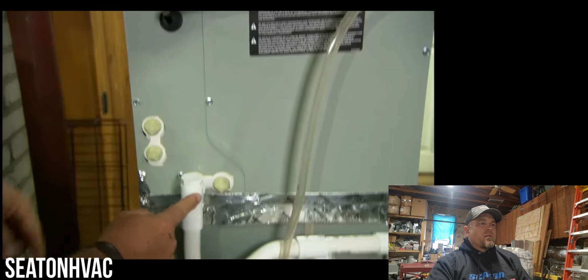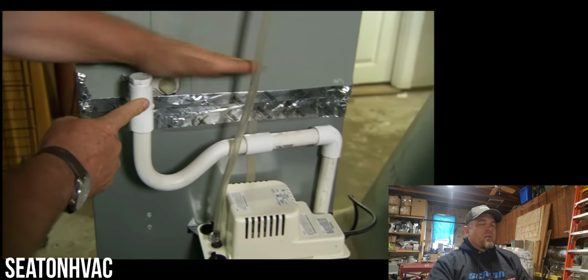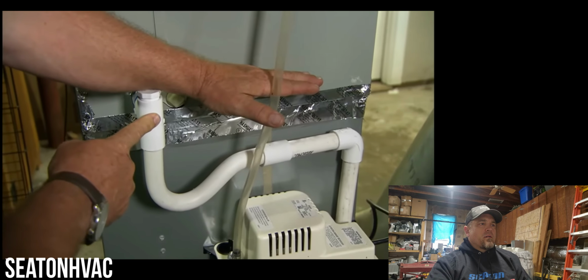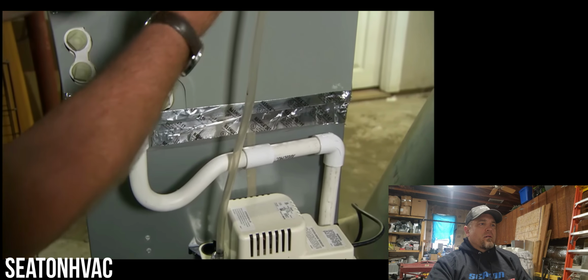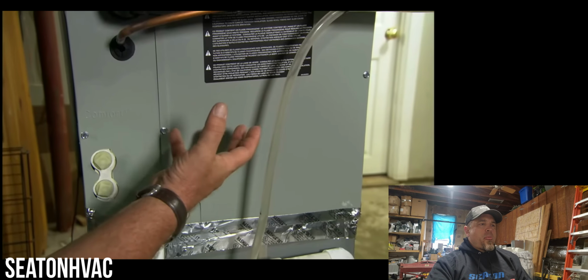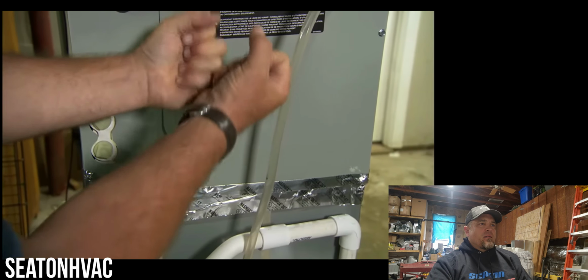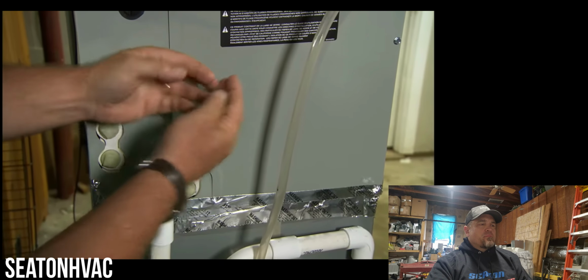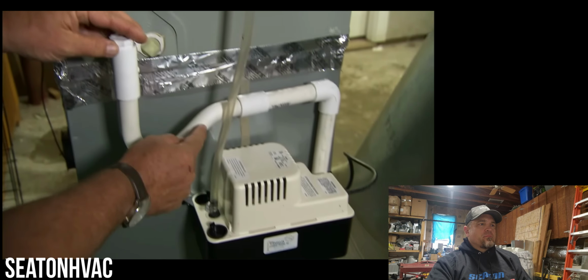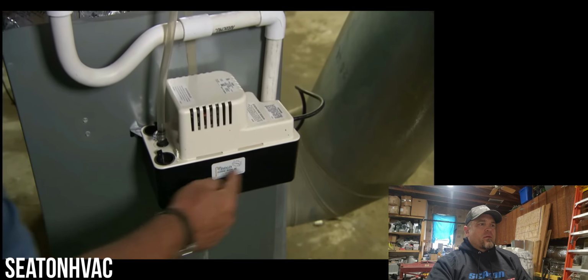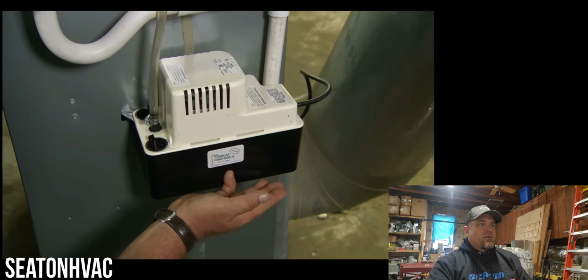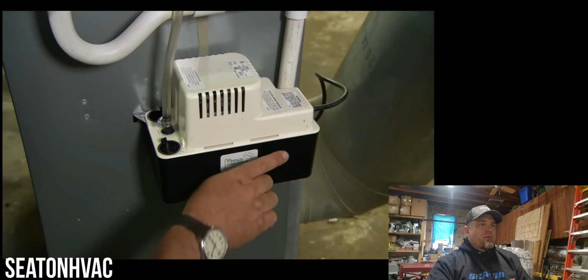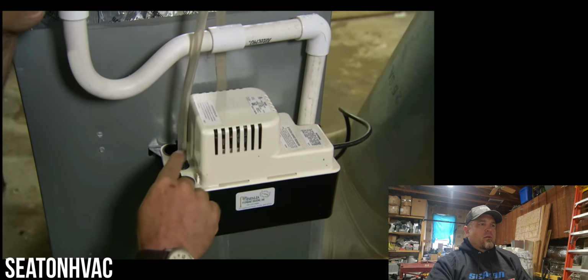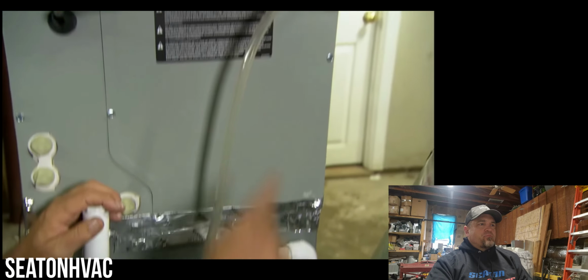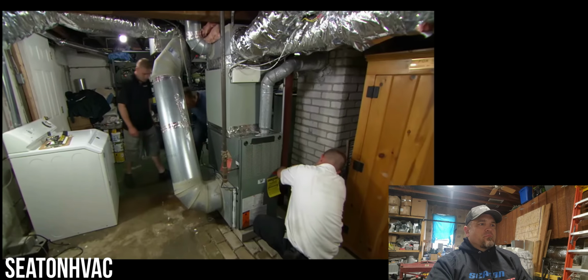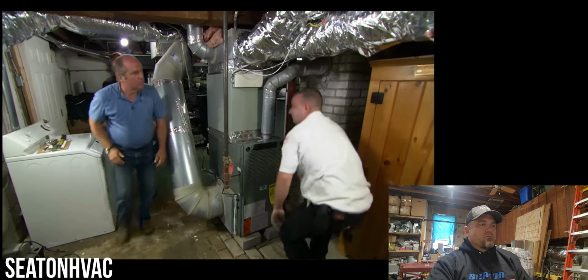Right here you can see the PVC connection to the condensate drain, which is right down at the bottom. Anytime we air condition, the air comes by that coil and we make the air cold, but one of the byproducts is all the humidity has to have a place to go. It turns into what they call condensate. It comes down through here, through a trap, down into this reservoir right here. There's a little float in there. When the water level rises, the float comes on, brings on a pump, and sends that water out to the drain over there. Now it runs on 110 volts, and Keith, you were working on that, right? Yeah, everything's all tied in over here.